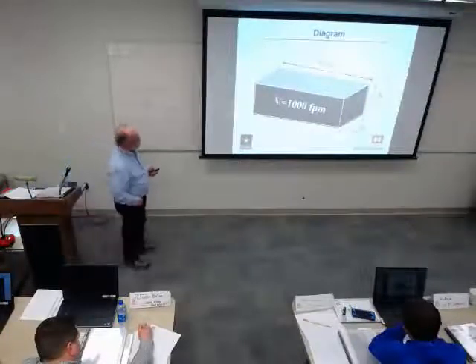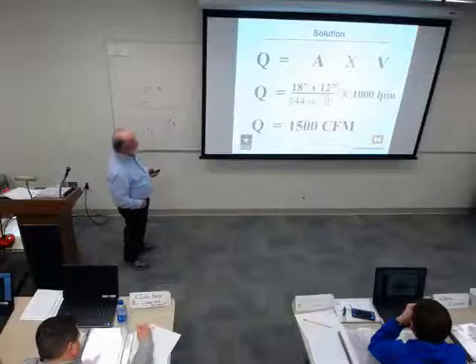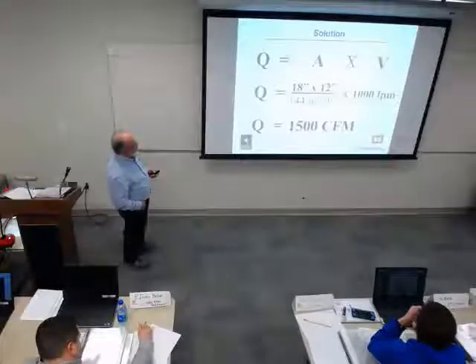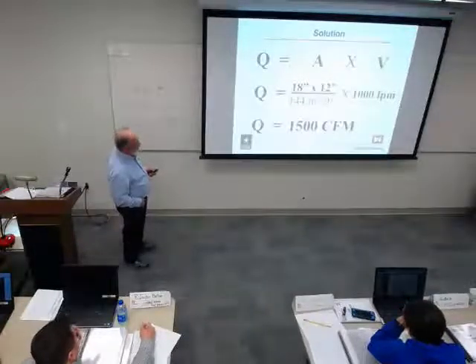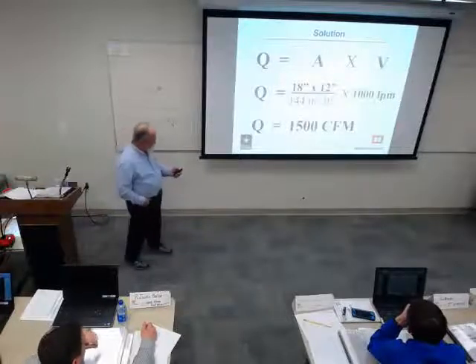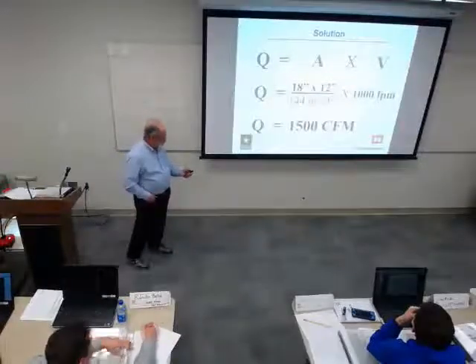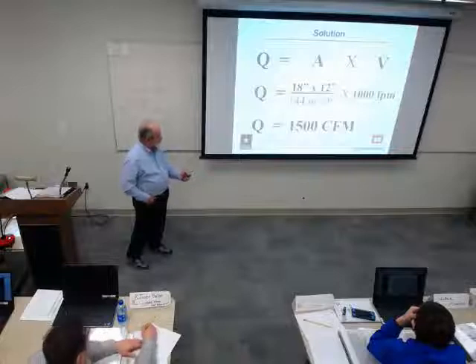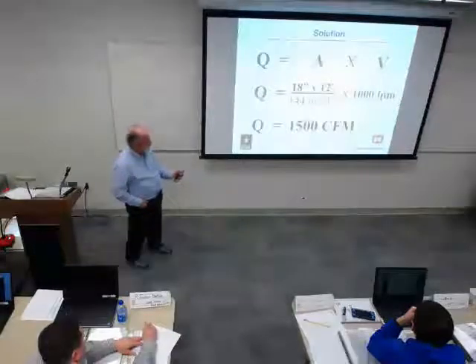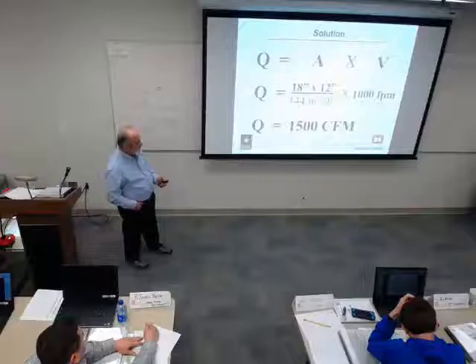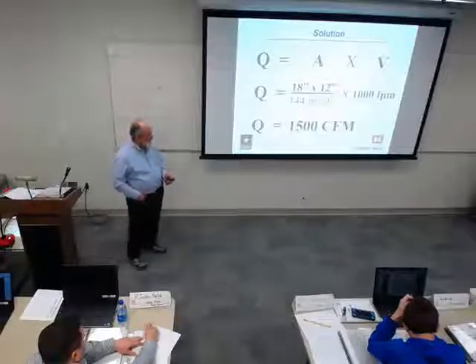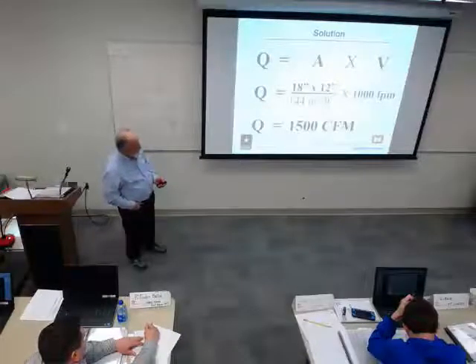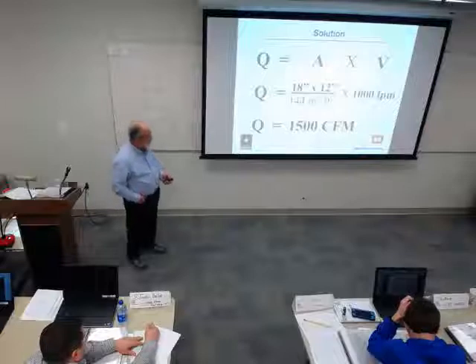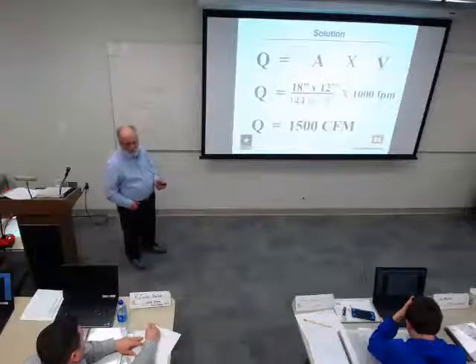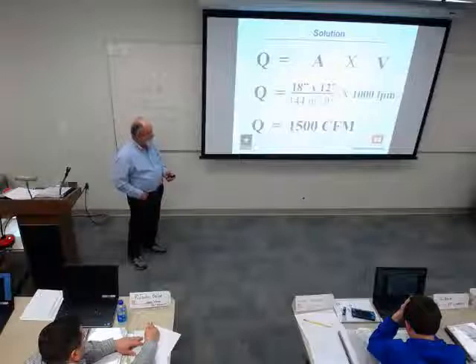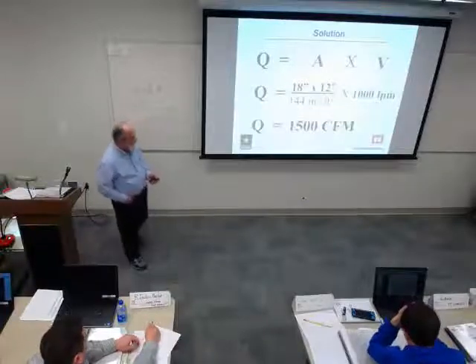Let's look at how we solve this. Our flow rate is going to be equal to the area times the velocity. And this first thing right here is area. And I'll show you where the 144 comes from. We have 18 times 12 divided by 144 times 1,000 feet per minute. And we carry that out, we see that we've got 1,500 CFM.